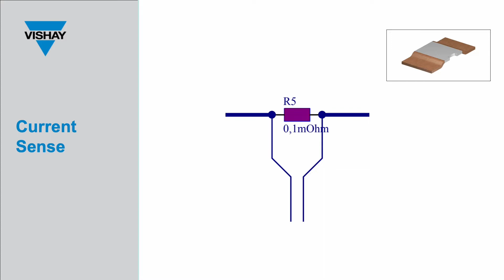However, I wanted to take a quick sidebar and explain why a current shunt technology was selected for this design. In most high current applications like this one, the current needs to be monitored for control purposes or overload protection. There are two methods that are commonly used for this purpose: a resistive current shunt and a Hall effect sensor. A Hall effect sensor is relatively simple to implement as a turnkey solution compared to a current shunt, which requires some additional feedback circuitry, but it can suffer from the following disadvantages: low linearity over a wide current range, offset error due to wide variations in the temperature.